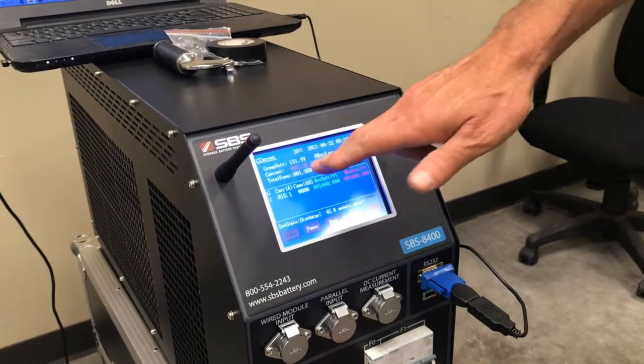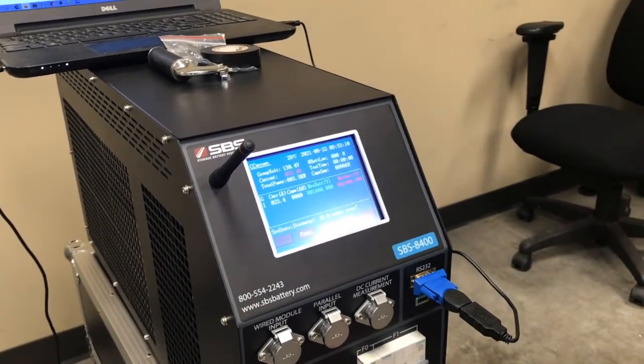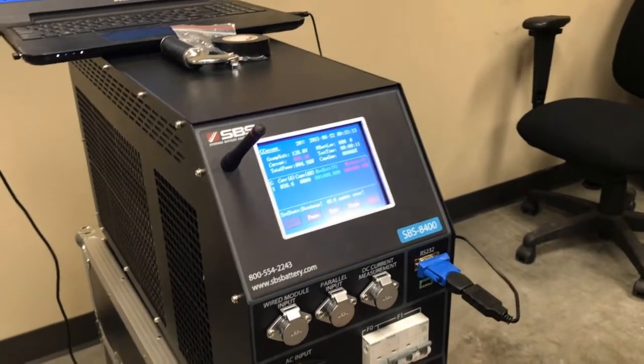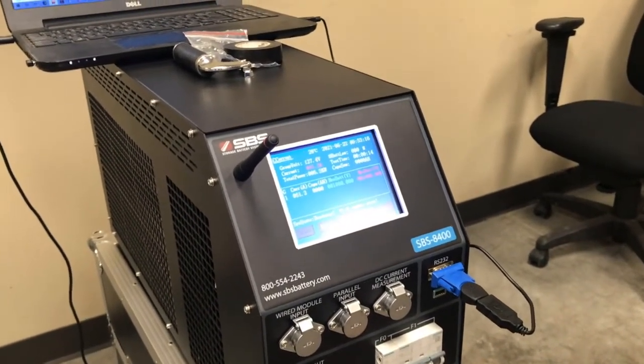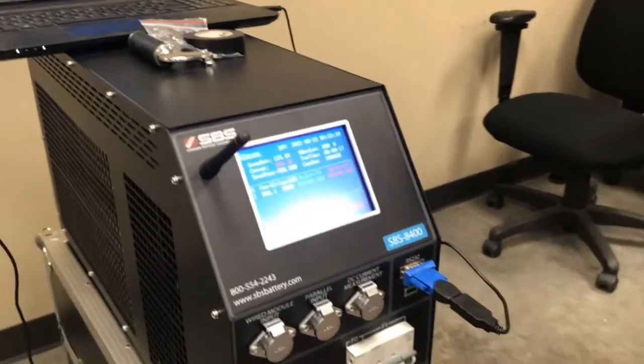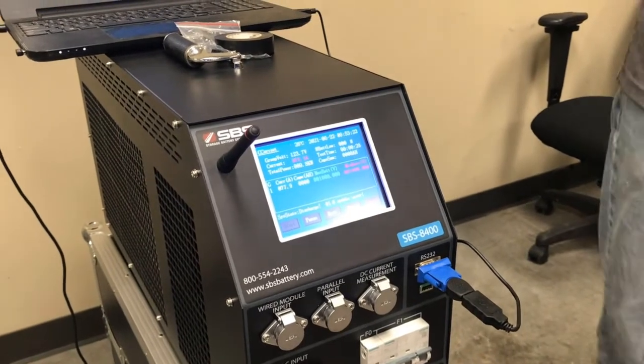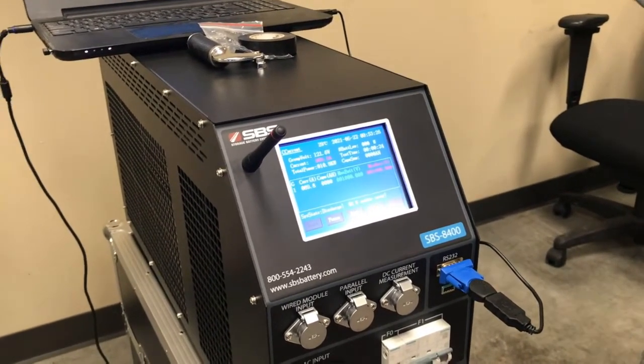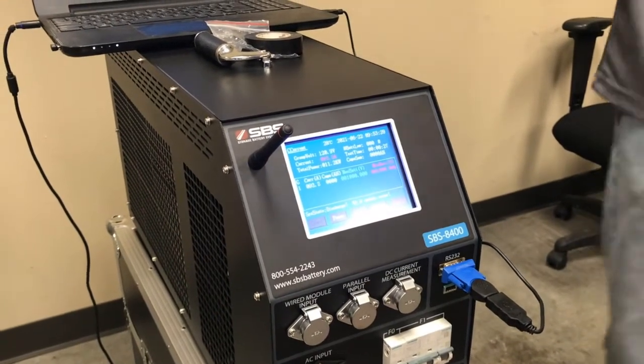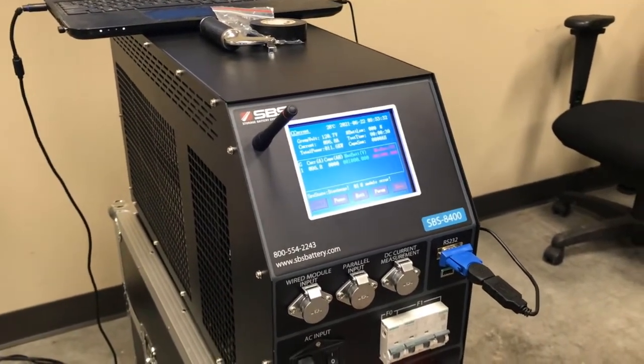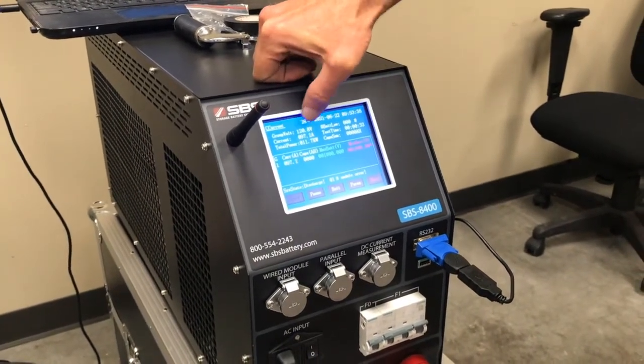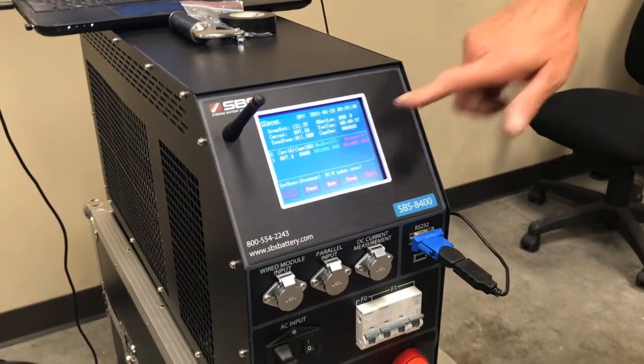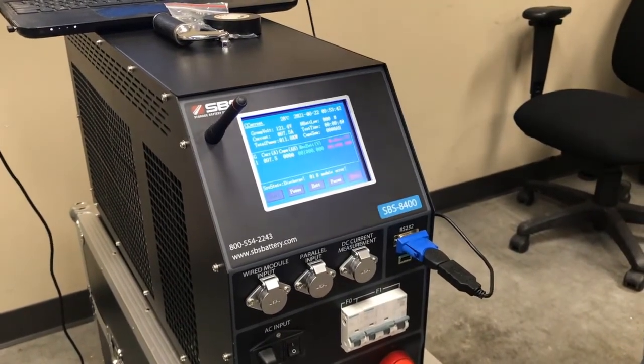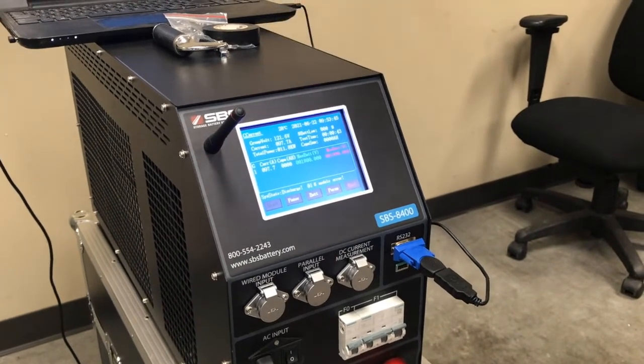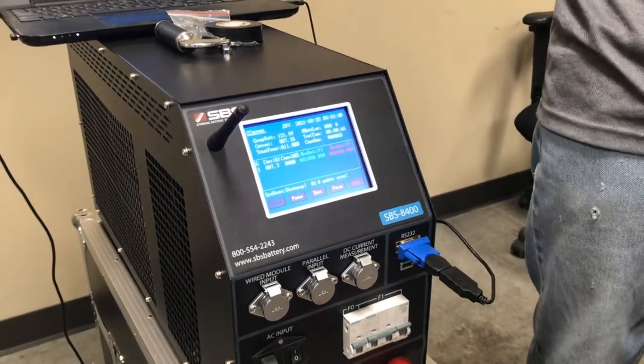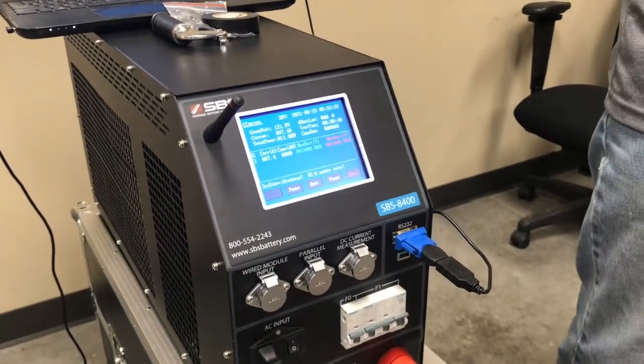I see my battery voltage start to collapse as the current starts to build up on the load bank. And that's that coup de fouet in the battery discharge curve as the chemistry tries to catch up with the demand of the current on the battery. Within the first 1 to 3 minutes, I should see a slight recovery in the voltage as the voltage comes back up as the chemistry catches back up with the load. And then from that point on, I'll see a stable DC voltage over the course of my test. Now you can see my DC voltage is starting to climb back up. It went from 120 to 121, 121.5, 121.6. So that recovery has already happened now that the load is steady at that 97.3 amps.